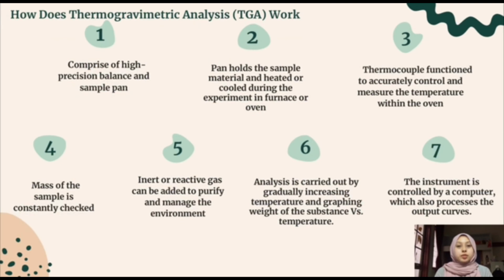How does thermogravimetry work? This machine comprises a high-precision balance and a sample pan. The pan will hold the sample material and is heated or cooled during the experiment in the furnace or oven. The thermocouple functions to accurately control and measure the temperature within the oven. The mass of the sample is constantly checked.